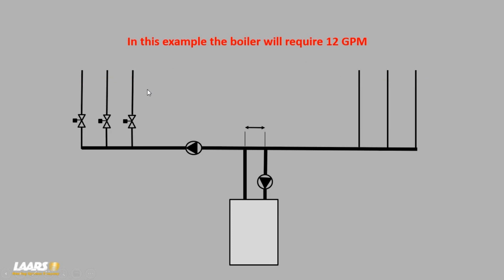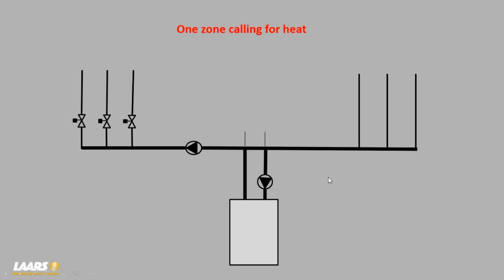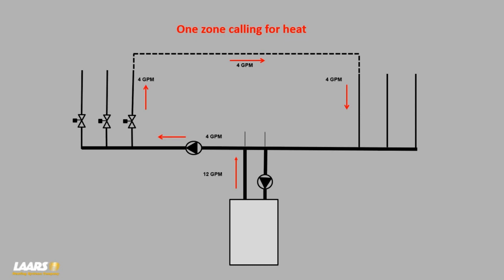In this example, if a boiler requires 12 GPM, the pump comes on, we're going to pull 12 GPM off the manifold and send 12 GPM right back to the manifold. So through the heat exchanger and back out. With one zone calling, 12 GPM to the manifold and 4 GPM travels down the manifold. Why only 4? Because a 3/4-inch pipe in this example can only carry 4 GPM. So it travels through the zone to the return manifold.